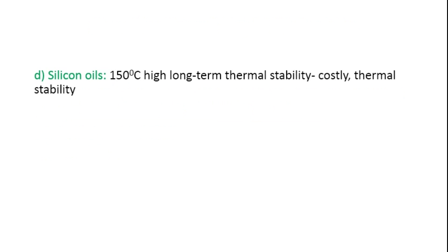Then we have silicone oils, which are the alternative for PCBs, but these are very expensive. Even at a temperature of 150 degrees Celsius they exhibit high long-term thermal stability, but because they are costly they are not generally affordable. We also have two types of synthetic esters: organic esters and phosphate esters. Organic esters have high boiling points relative to their viscosity and therefore have high fire points. They have a good viscosity-temperature relationship and are extensively used in capacitors.